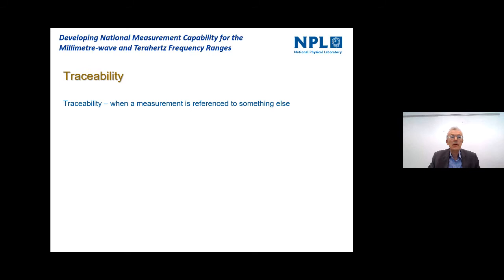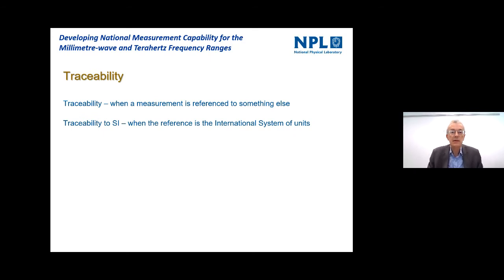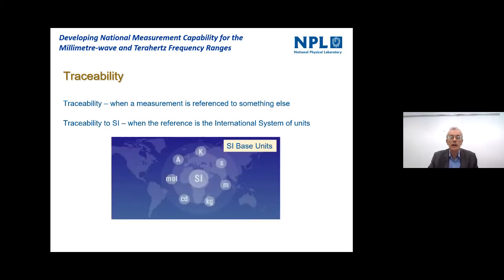The other parameter I talked about was traceability. This is when measurements are linked to references. So this is also very important, that measurements are traceable to an independent reference. And the most important independent reference is what we call the International System of Units. So this is the system of units we have globally in the world that links all measurements back to the basic quantities such as the meter, the kilogram, the second, etc. If our measurements are linked to these base units, then they can be compared meaningfully with other measurements.